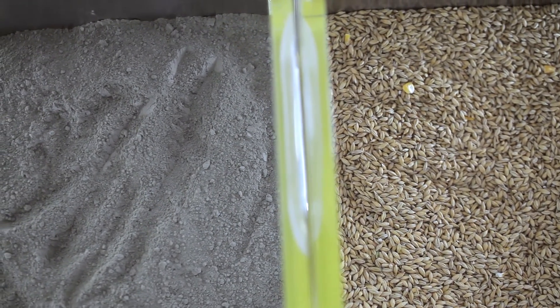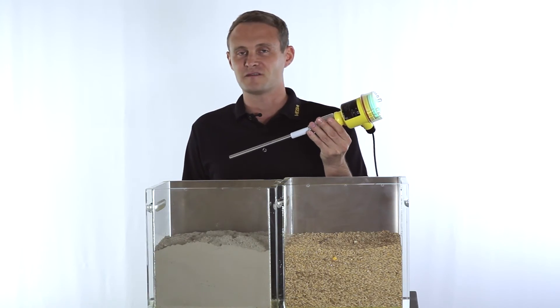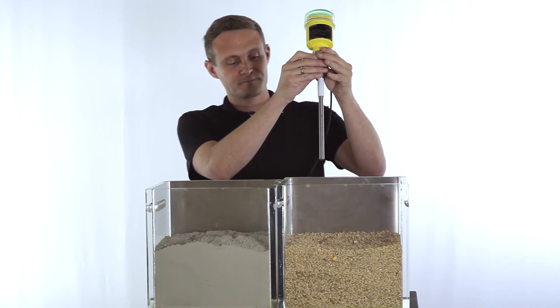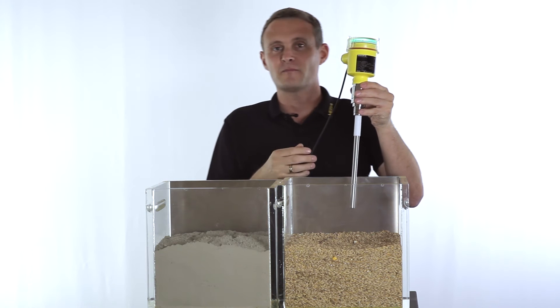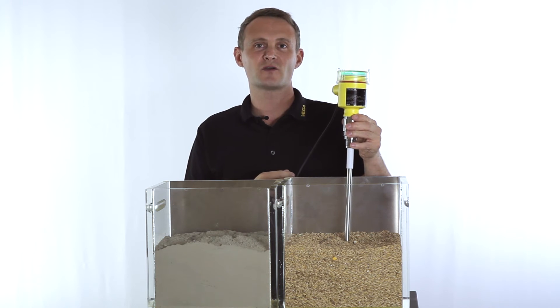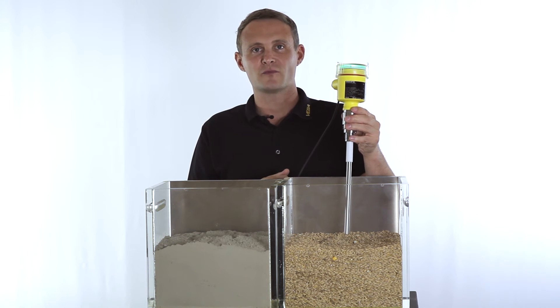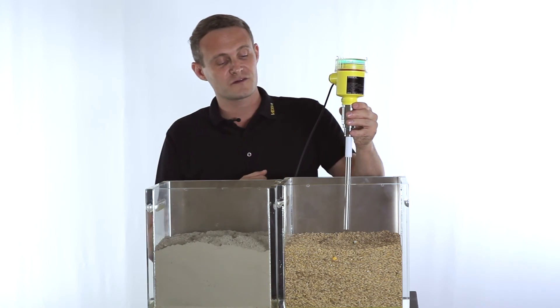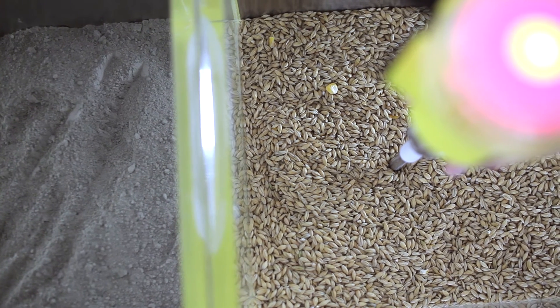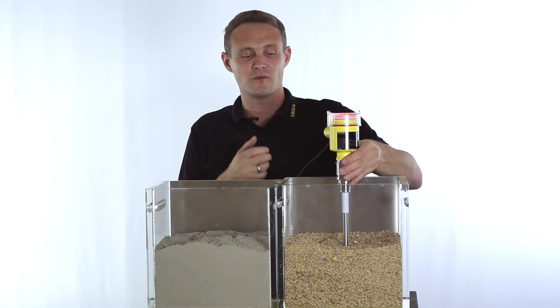Another possibility to detect the level of bulk solids is using a capacitance probe like this VEGACAP series 60. The working principle: the probe is submerged and therefore the capacitance changes, and this capacitance change is then analyzed and converted into a switching output. We can now see how this works, for example with grain filling — the probe is submerged and a switching output is generated to stop the filling process.